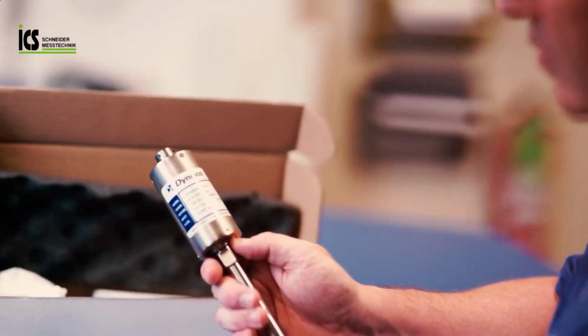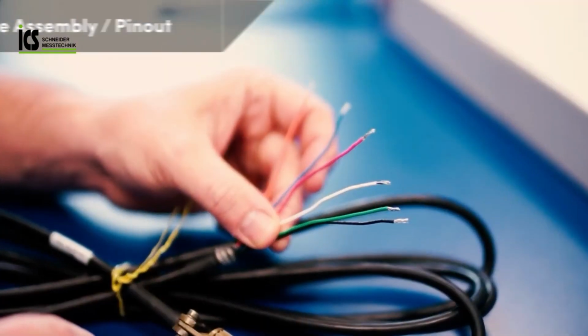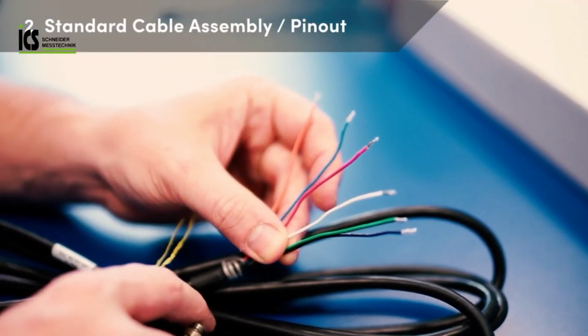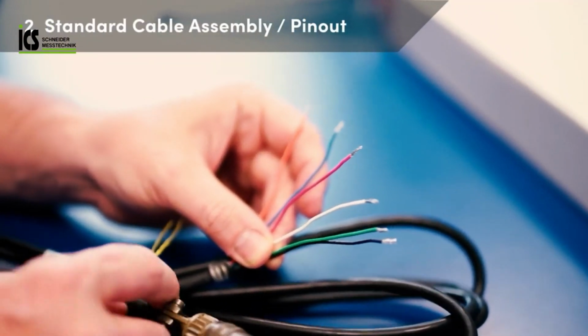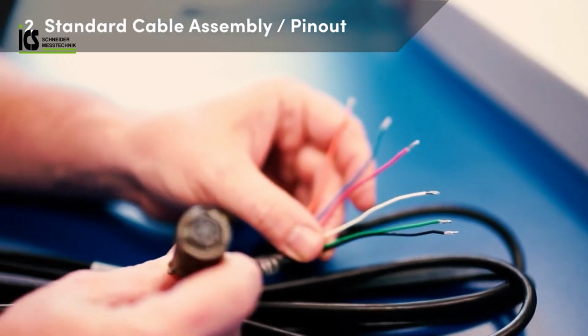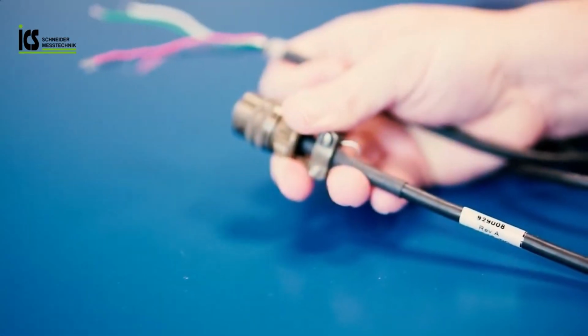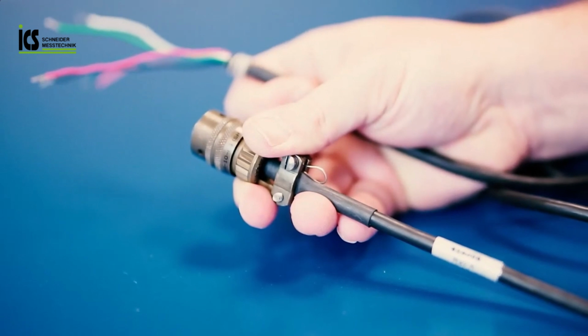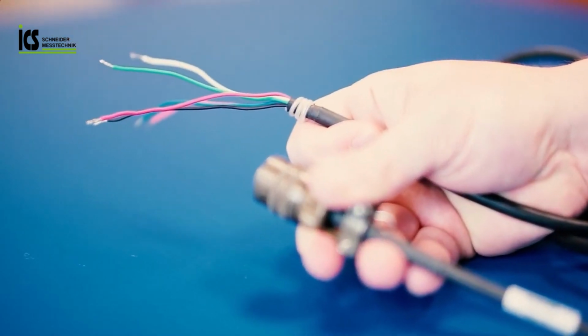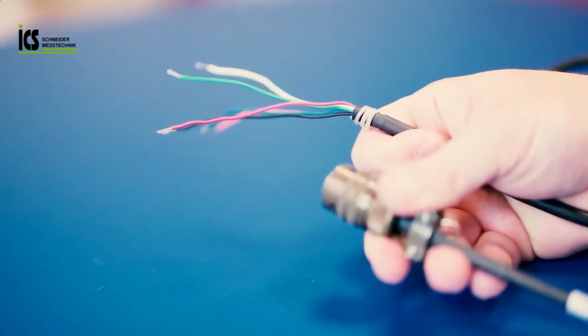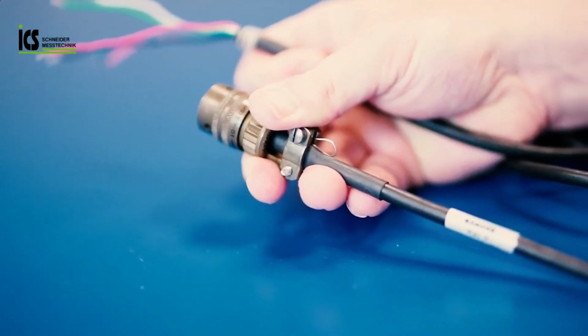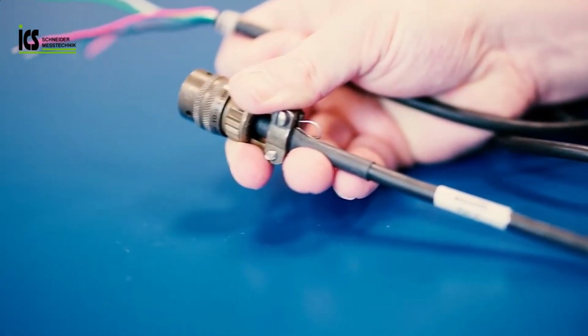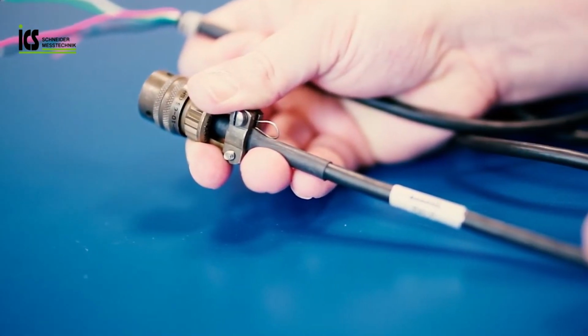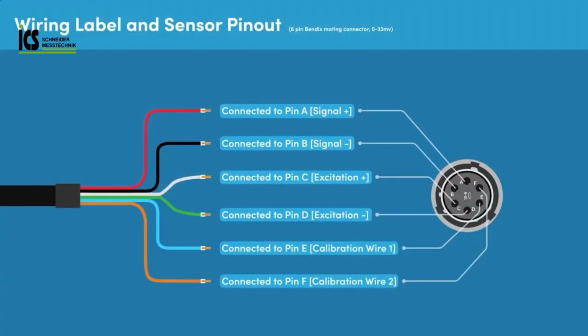Once the sensor has been checked for damage, the technician selects the proper cable assembly to use with the pressure sensor and instrument. In this case, the cable assembly selected has a length of 10 feet and includes a 6-pin Bendix mating connector. There are 6 bare wires on the end of the cable, which are colored to identify the corresponding pin and function. The standard connection pin out for a cable used with a pressure sensor that has a 0 to 33.3 millivolt output would be as follows.